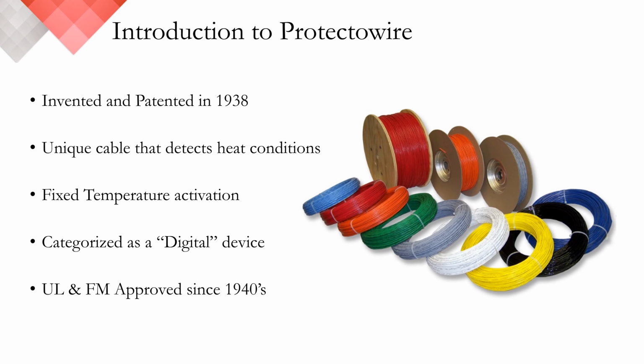Let's start with a quick introduction. Protectowire linear heat detectors are a series of fixed temperature devices. Their unique design enables their use in several challenging applications where conventional detectors simply cannot reach. Except for fiber optic, Protectowire linear heat detectors are categorized as a digital device, which is simply to say the condition of the device is either on or off. The first linear heat detector was invented back in 1938 by Gerald Holmes, the founder and original owner of Protectowire, and has been listed with both UL and FM since the 1940s.